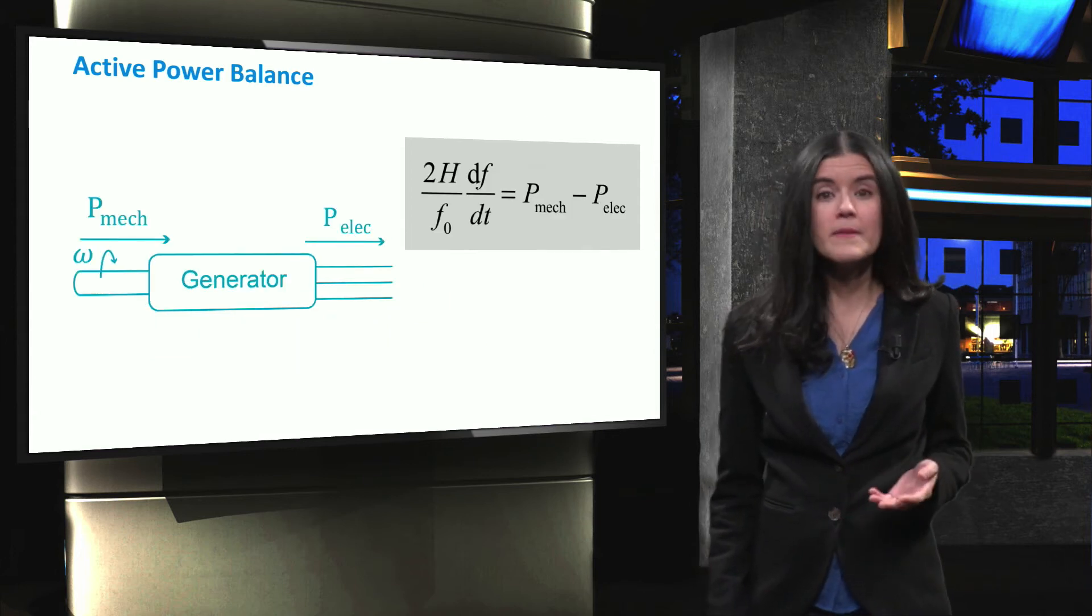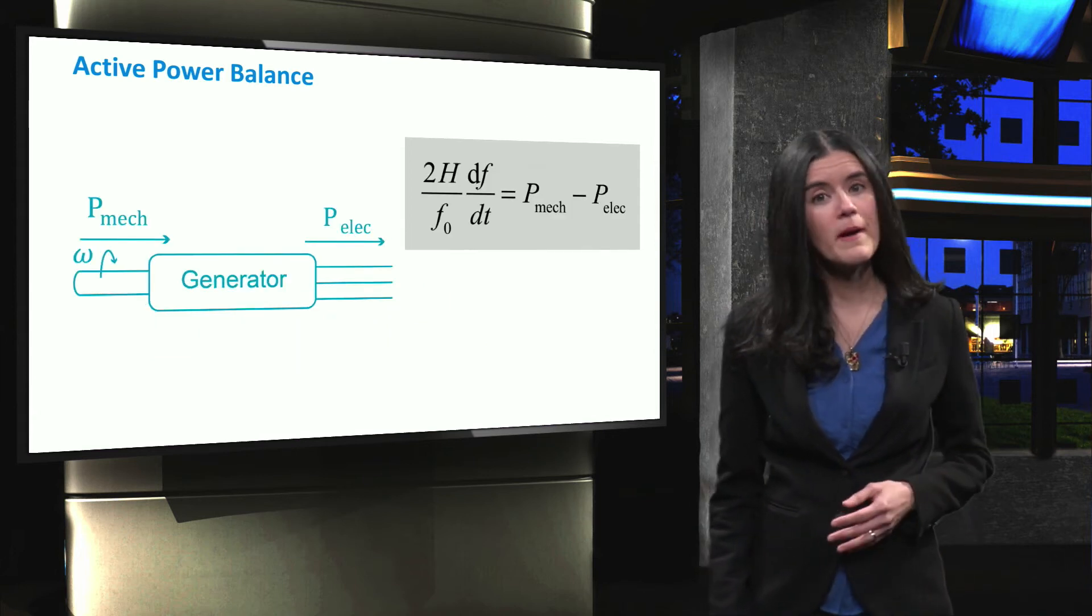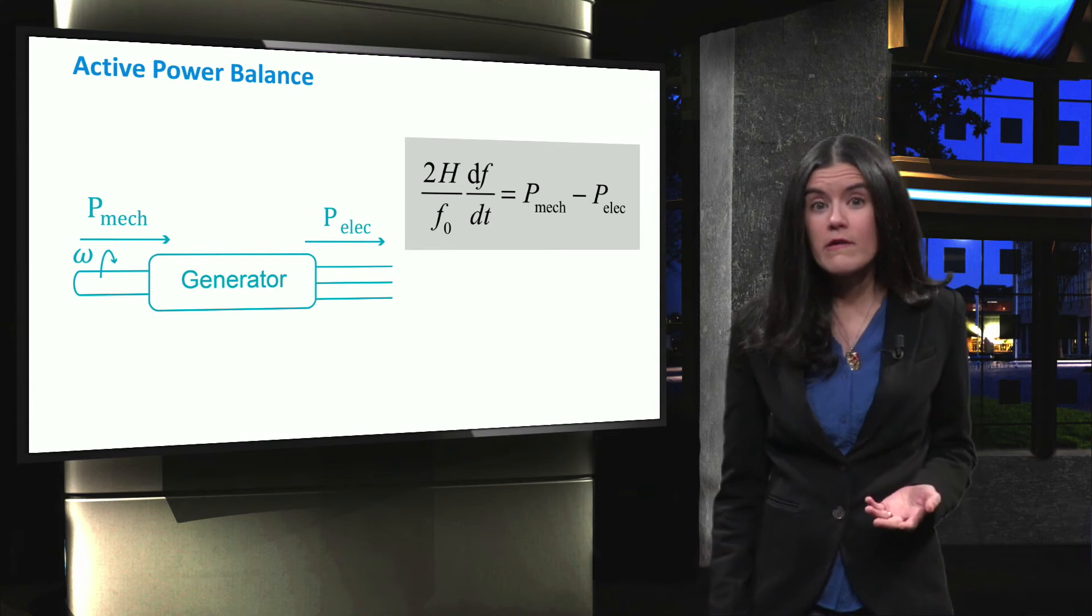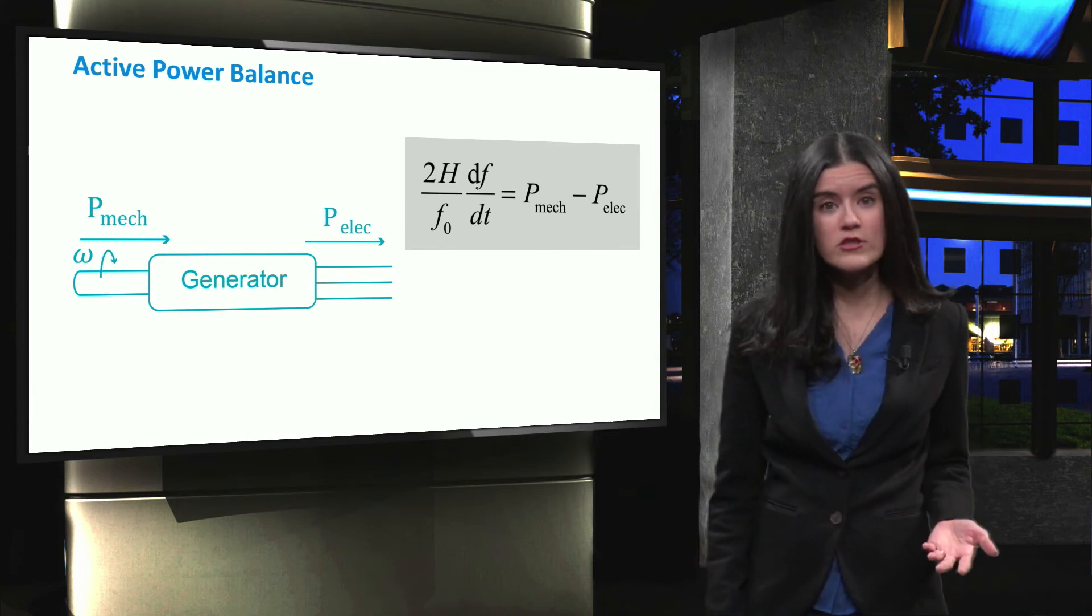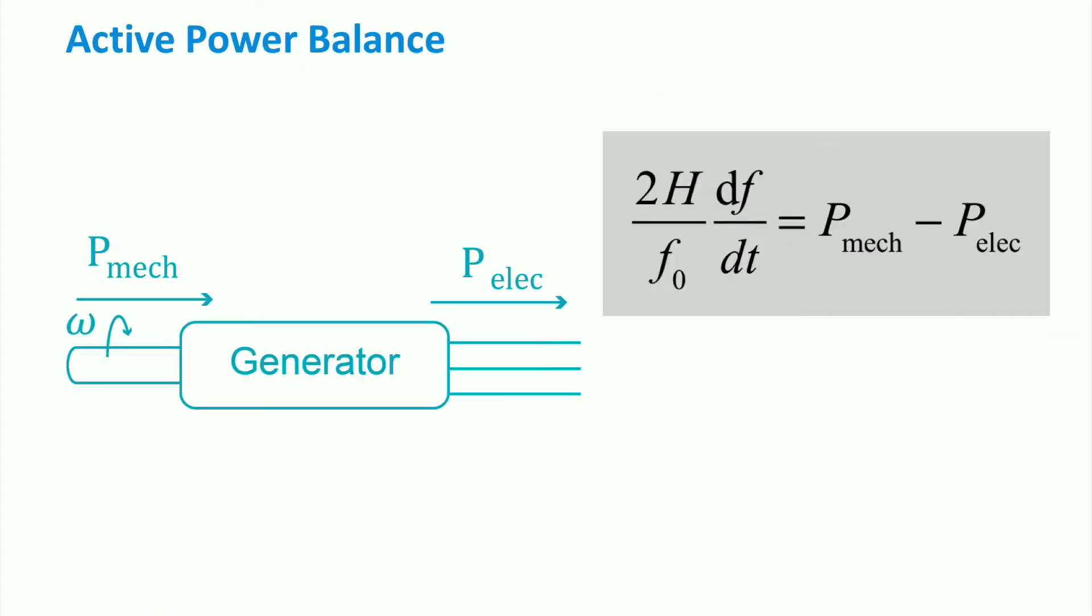When there is a mismatch between the mechanical and electrical power, the rotor speed or frequency changes according to the total inertia constant of the rotor shaft. The formula shows the relationship between the accelerating power and changes in frequency, here represented by its time derivative.